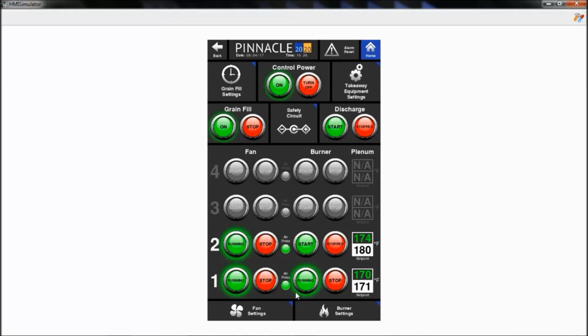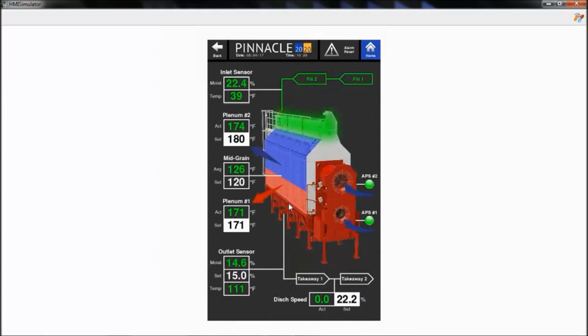Once the purge is finished and we detect a flame, you'll see running here. And once again, if we go to our overview page, we can see plenum number 1 has cold air coming in and hot air coming out because the burner's on. Plenum number 2 has cold air coming in and cold air coming out because the fan's on but not the burner.